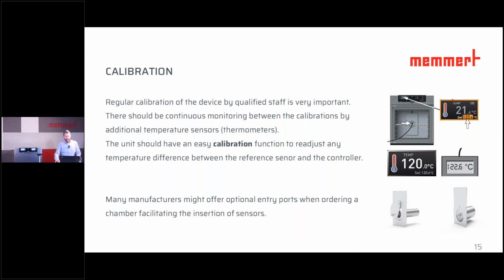Many manufacturers offer optional entry ports when ordering a chamber, facilitating the insertion of sensors. Entry ports are usually installed on the side or the rear wall of the appliance. However, a few manufacturers also offer the option of freely defining the position of an entry port. The entry port should always be closed by means of a plug or a flap when the unit is in operation.